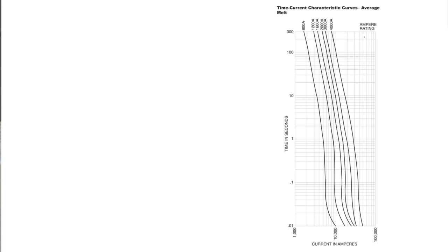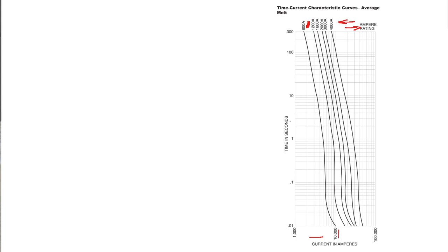Let's first look at the different axes of the chart. At the top we have the amp rating of the actual fuse. At the bottom we have current in amps, which is the fault current. So if there was 10,000 amps of fault current, that would be represented here. On the left hand side we have time in seconds, which represents the trip time of the fuse to open the circuit—basically how long will it take to de-energize the circuit.